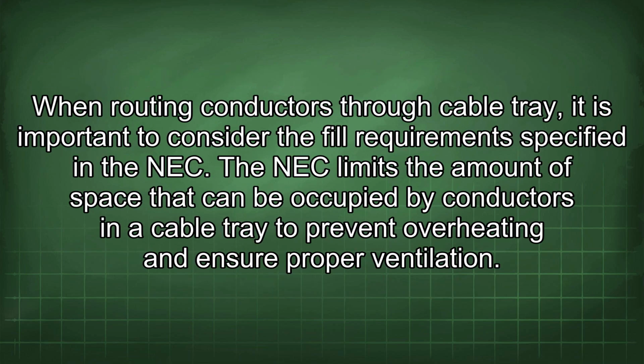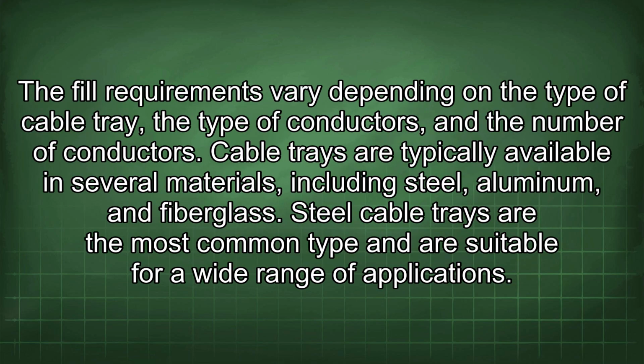When routing conductors through cable tray, it is important to consider the fill requirements specified in the NEC. The NEC limits the amount of space that can be occupied by conductors in a cable tray to prevent overheating and ensure proper ventilation. The fill requirements vary depending on the type of cable tray, the type of conductors, and the number of conductors. Cable trays are typically available in several materials, including steel, aluminum, and fiberglass.